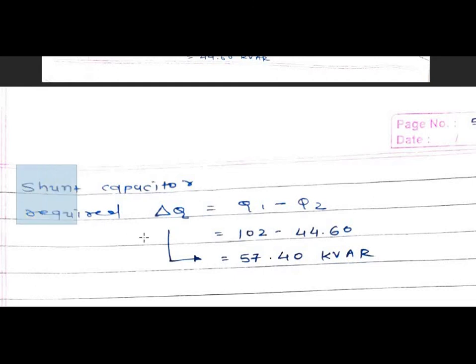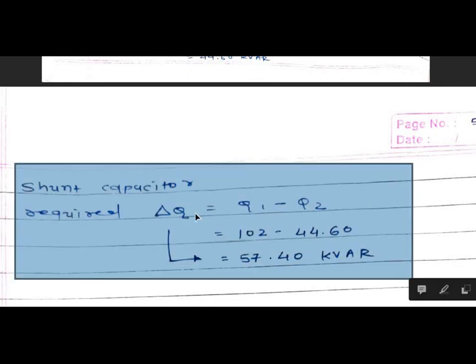The shunt capacitor required, delta Q, for improving the power factor from 0.7 to 0.95 is given by delta Q equals Q1 minus Q2. Q1 is equal to 102 KVAR and Q2 is equal to 44.60 KVAR, so delta Q is equal to 57.40 KVAR. This is the reactive power required to improve the power factor from 0.7 to 0.95. This capacitor value is 57.40 KVAR leading.